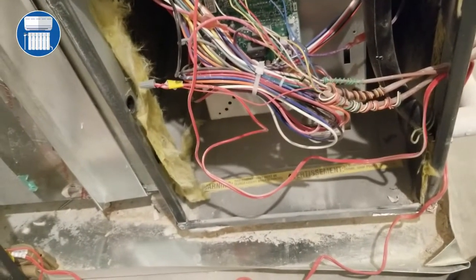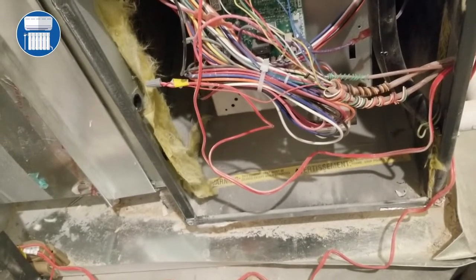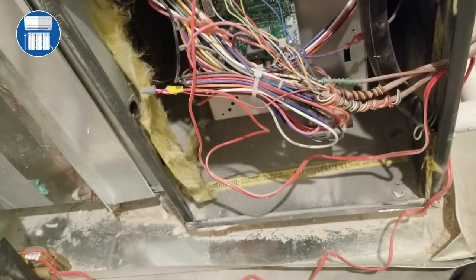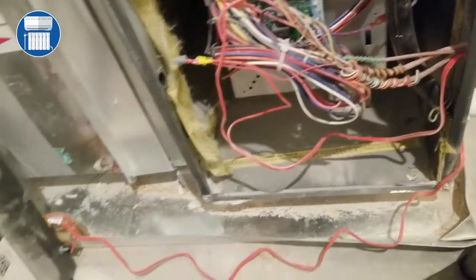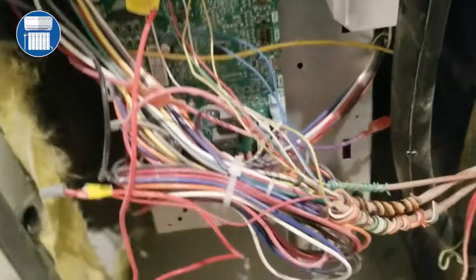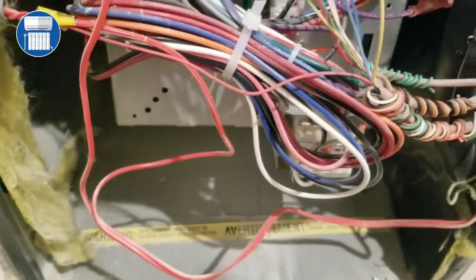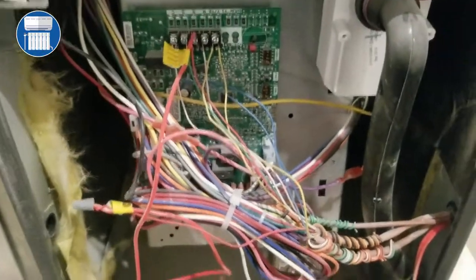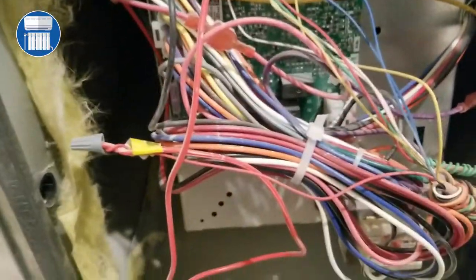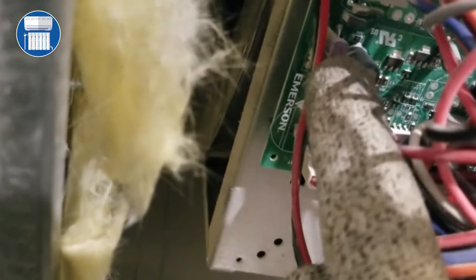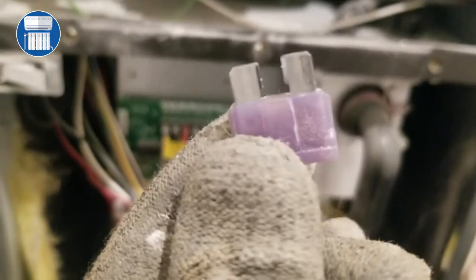I'm going to go through some of the most common problems, and then we're going to look at 7 flashes, which on this one is saying fuse, and this is one of the major problems I run into. I can't tell you how many times I've had to drive an hour to check a unit just to change a fuse, and how much that could cost. So you may want to change your fuse. This is your fuse right here. To see if it went bad, it's easy. You can just pull this out and look at it, and if you see any black spot within that fuse, you may want to change it.